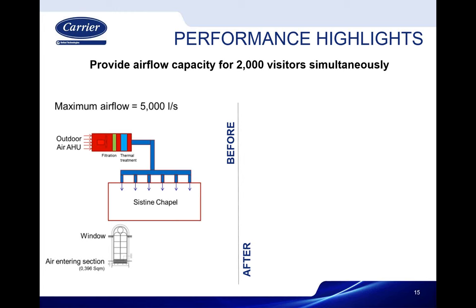Six outlets underneath the windows, blowing the air in, no return. I don't know if you noticed the details when you visited, but there's a little return in the center of the floor, and the doors where you'd come in by the altar, or leave around the corner by the cantoria or in the back, were almost always left 100% open. The space was under positive pressure.